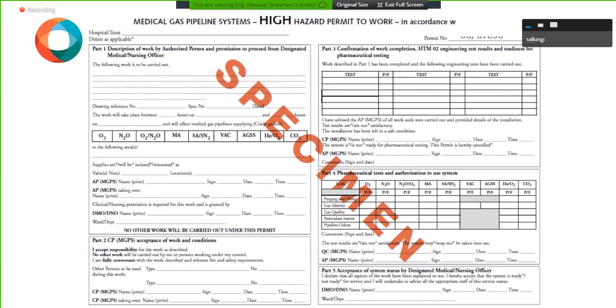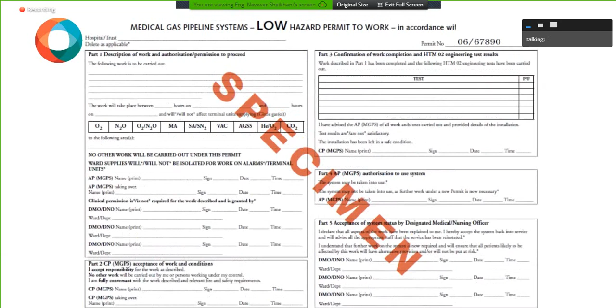Again, why have we chosen HTM? Because HTM said we have to use a medical gas pipeline permit to work, or work permit, depending on the hazard, whether high hazard or low hazard, and everyone should sign it. High hazard, we use it once we have a new line, new project, new extension. We have to shut off the pipe and construct a new extension. While low hazard is only once you just change or replace the outlet by a new one. It's low hazard.